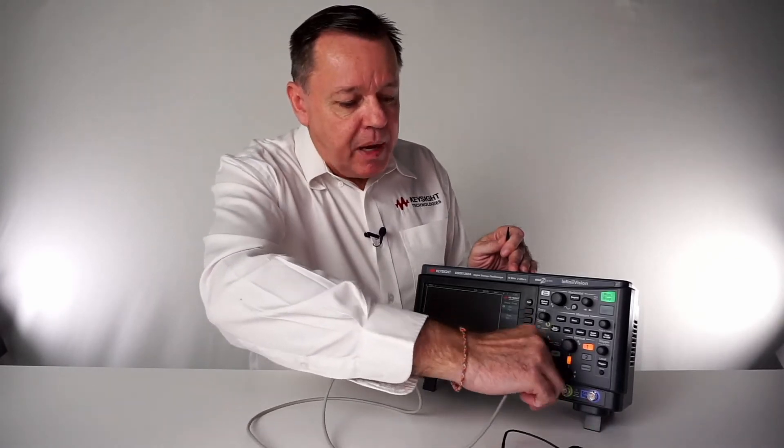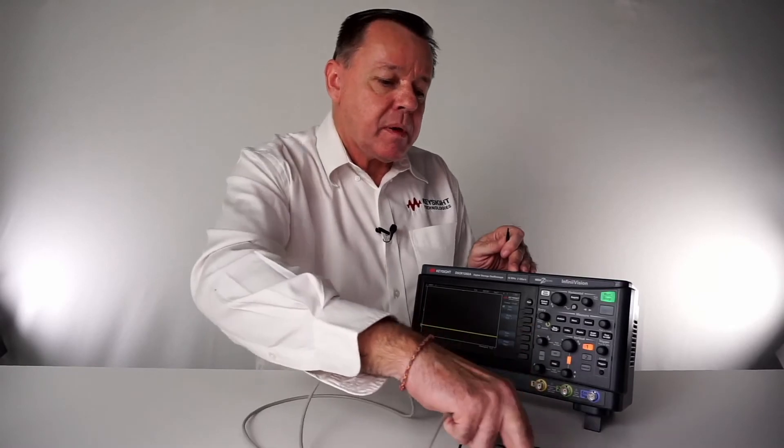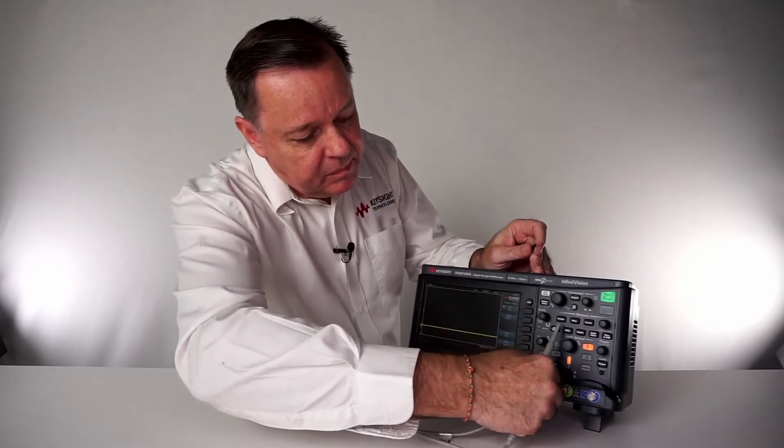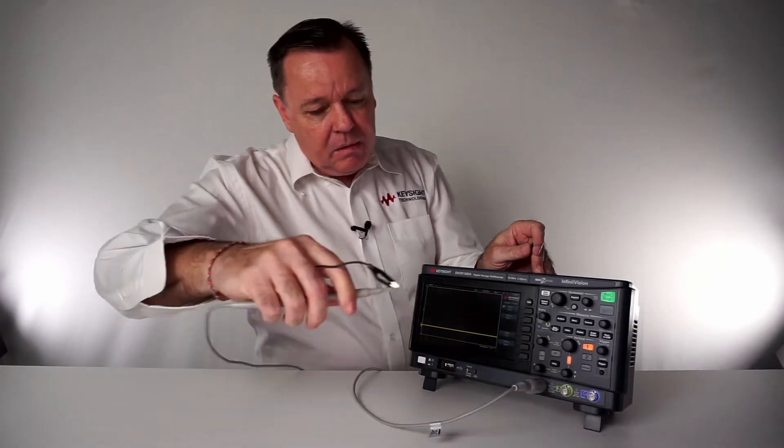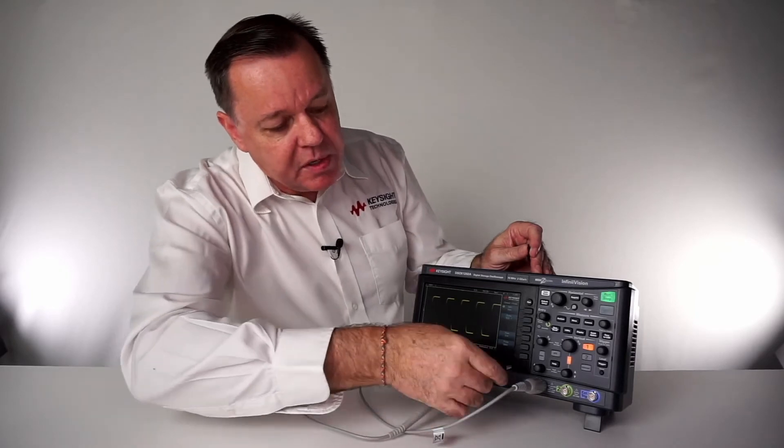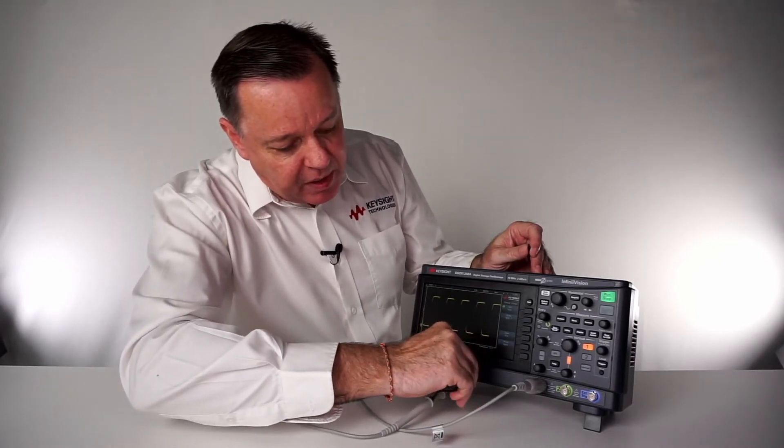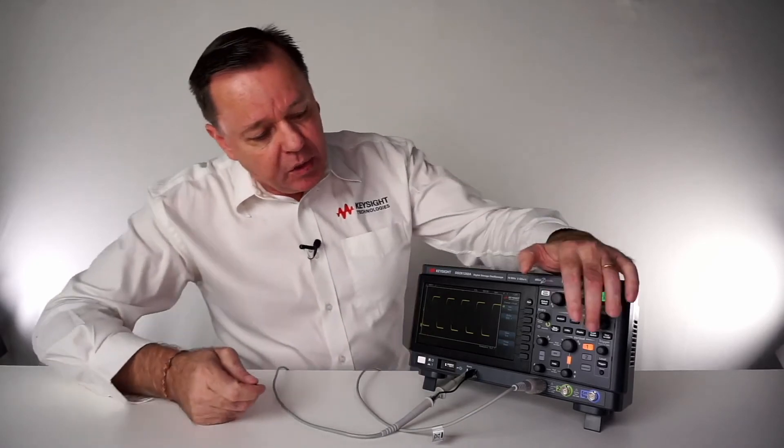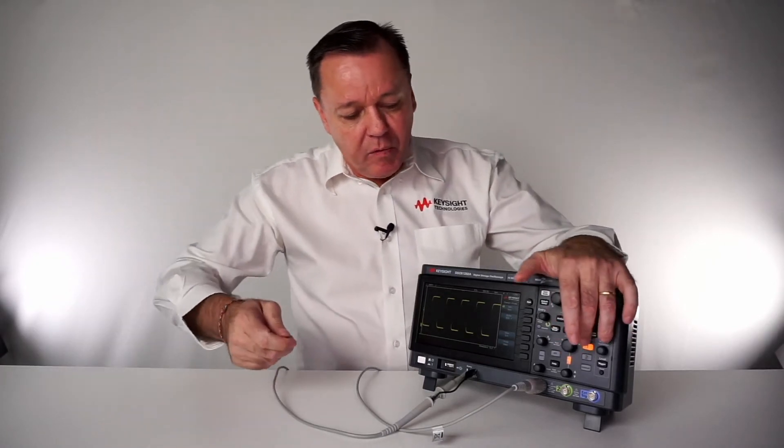I'll show you the same now with the other probe. Also hook that up. Of course, if you want to use two channels, then you would put the second probe on channel two, and of course then you also go to channel two for compensation.